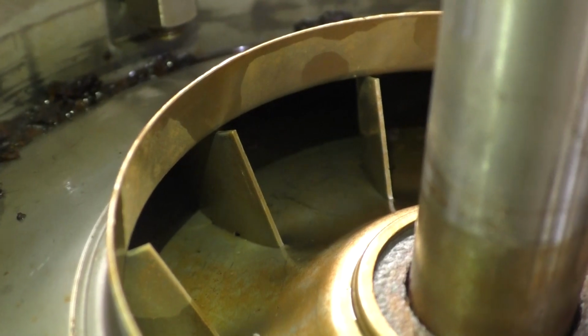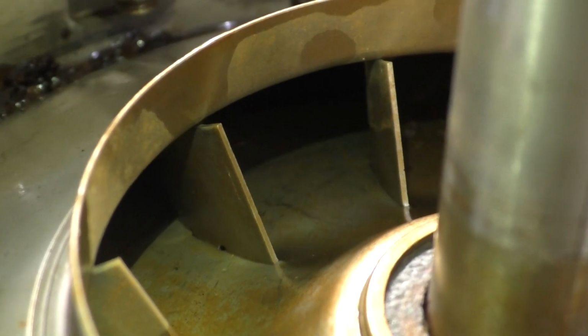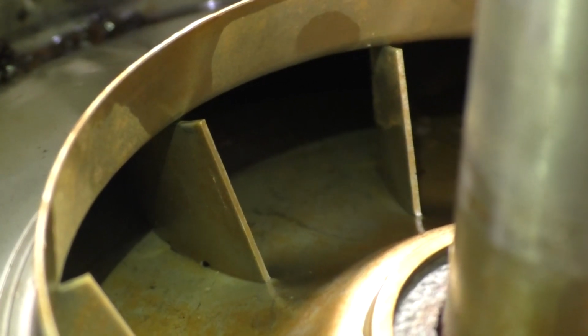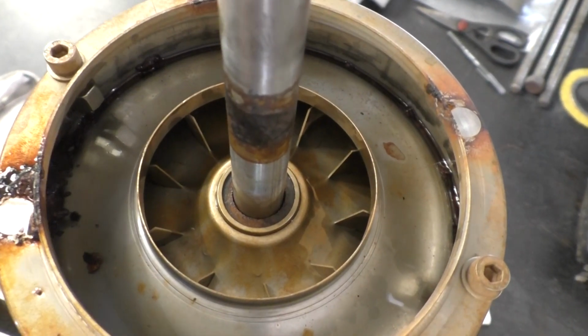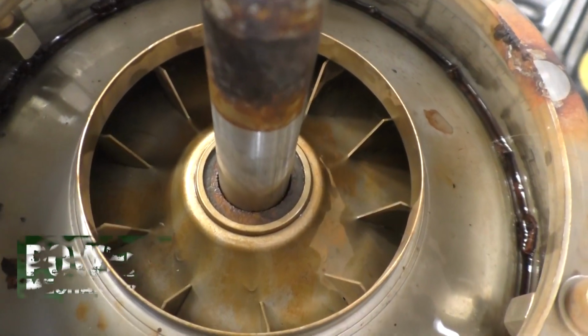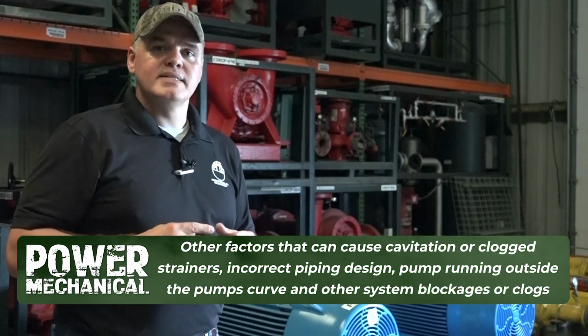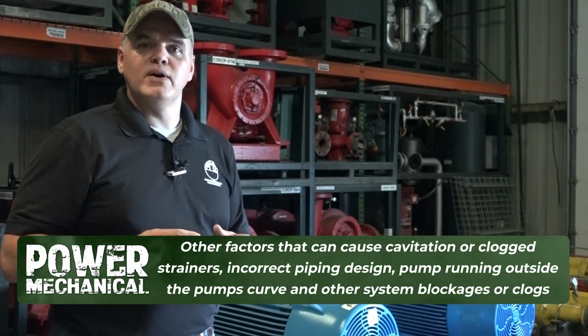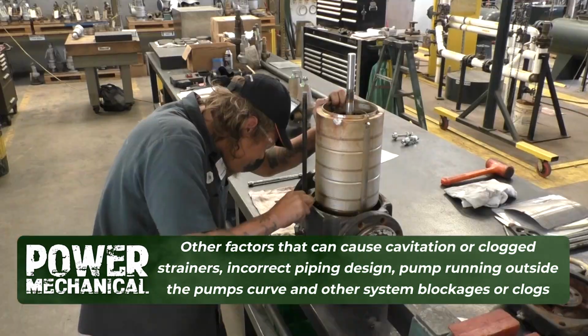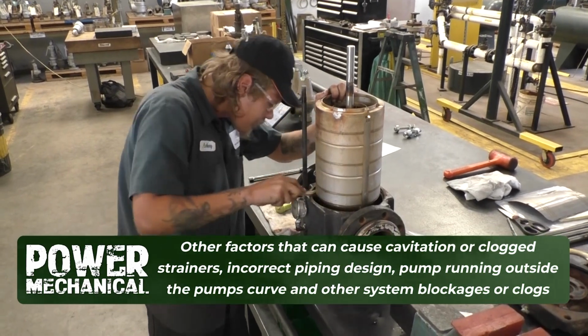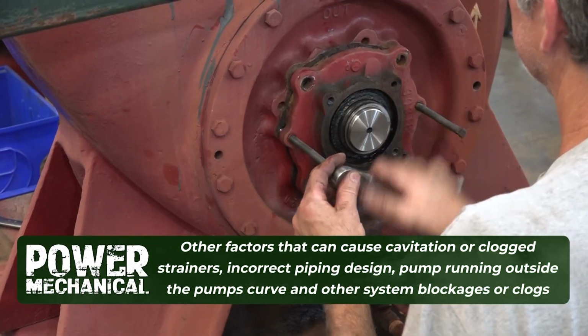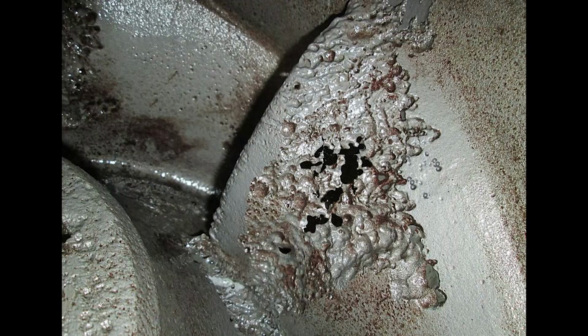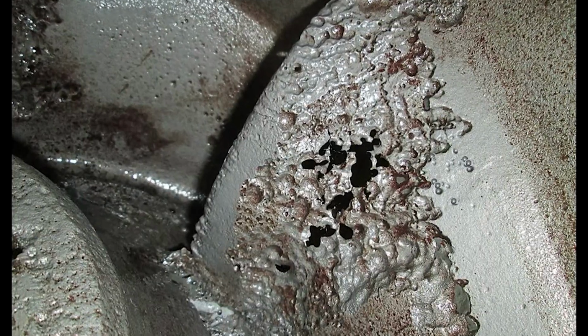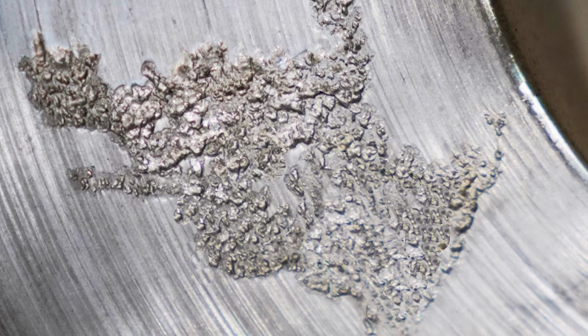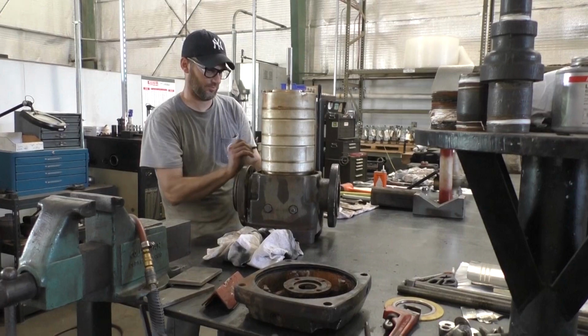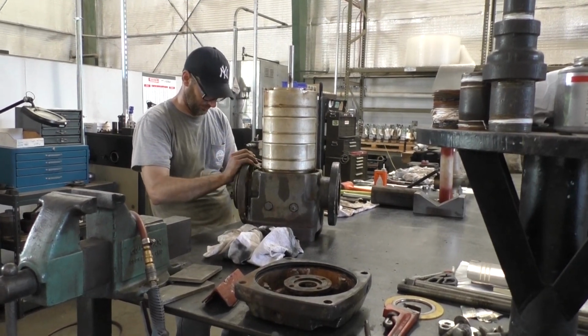The hammering is often described as sounding like sand or gravel inside the pump's casing, when in reality it's simply the bubbles imploding and causing vibration and mechanical damage. As the cavitation of a pump continues, the failure of the impeller is inevitable. Additionally, this vibration can lead to other mechanical and alignment issues that will ultimately destroy the pump. An impeller damaged from cavitation will often have an eroded or pitted look and will usually be damaged beyond the point of repair at this point.